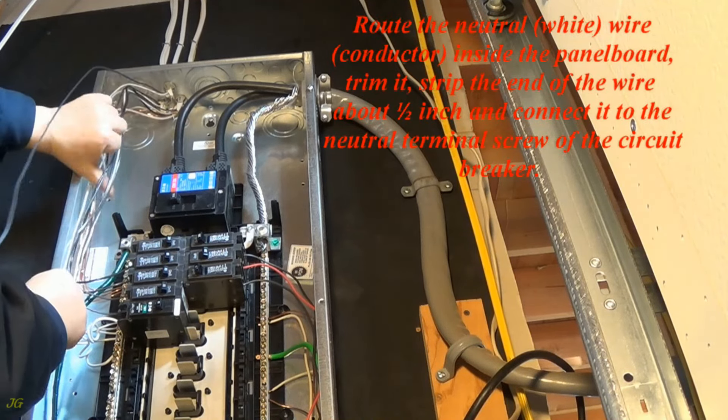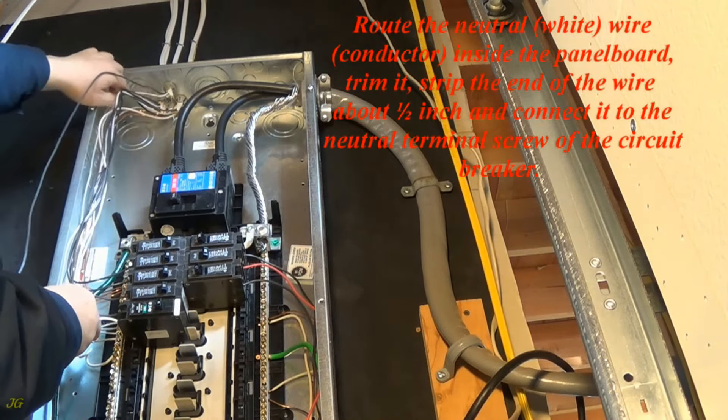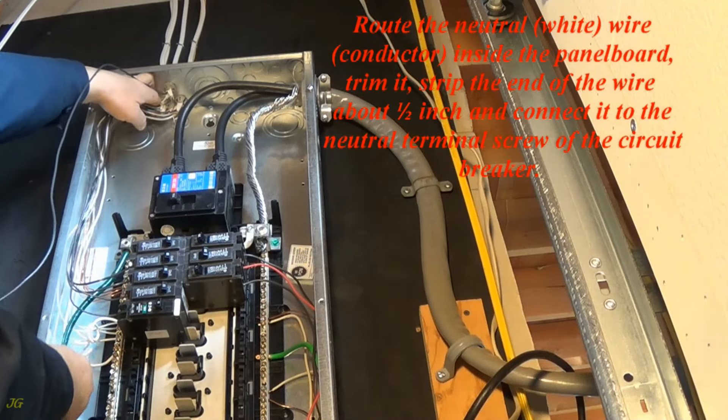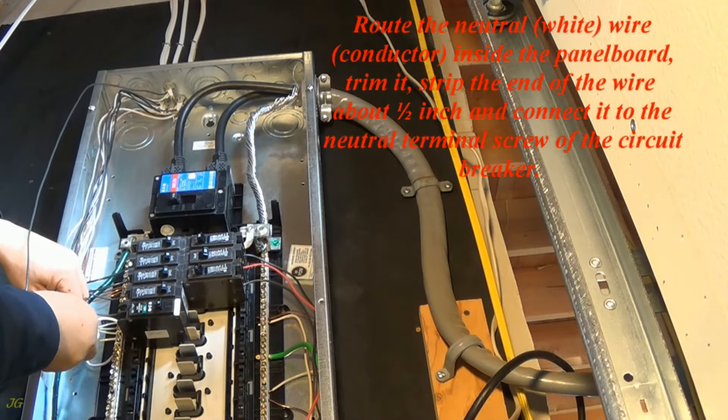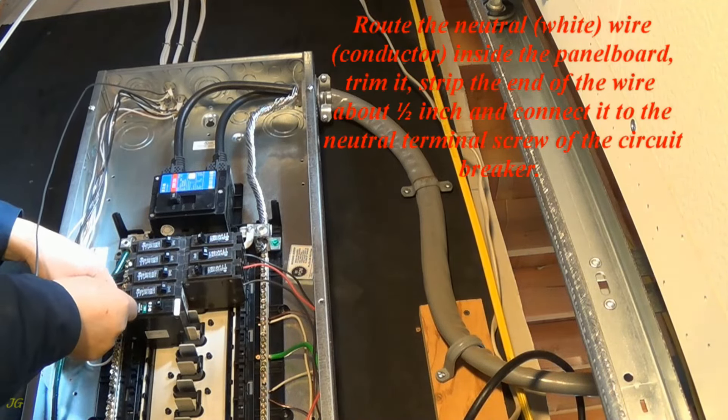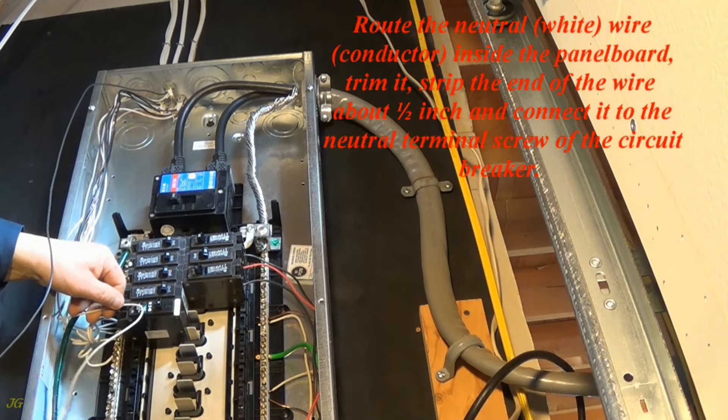Route the neutral, white, wire conductor inside the panel board, trim it, strip the end of the wire about one half inch and connect it to the neutral terminal screw of the circuit breaker.